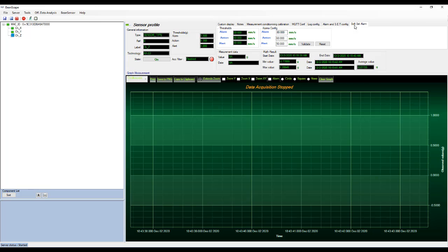Note here that for each sensor X, Y and Z, the three levels of alarms should not have the zero value at the same time. So you should enter a value different from zero in two different levels at least, otherwise you cannot perform a soft set data acquisition. Also, you should configure the threshold for each sensor X, Y and Z separately.